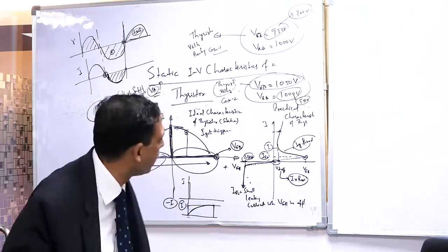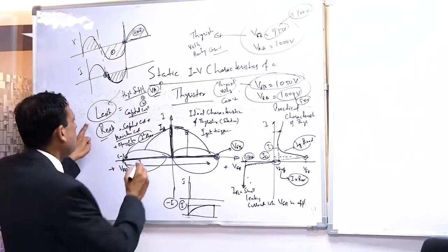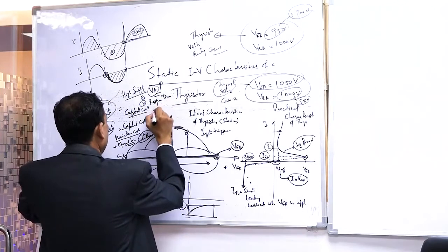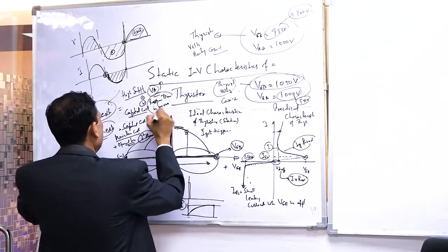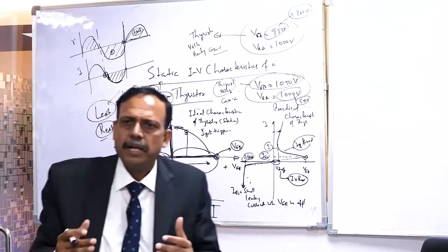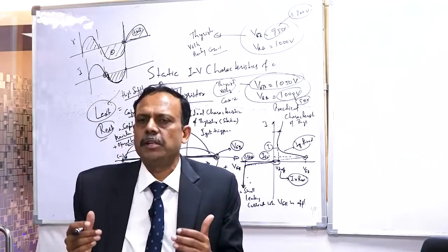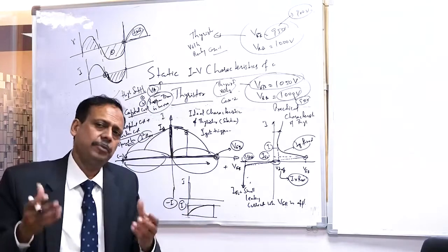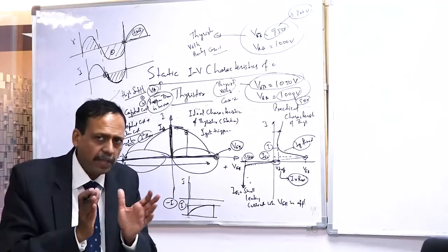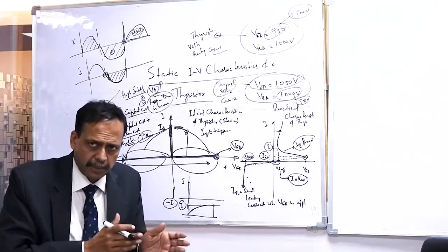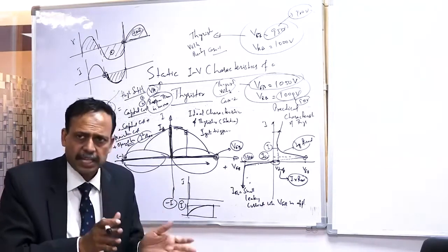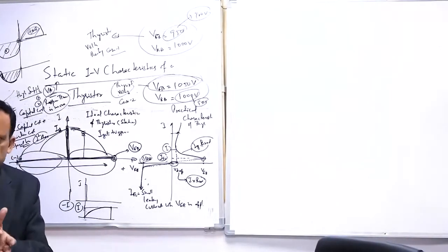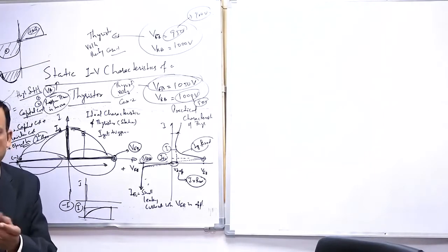Response time is poor when the inductance is used. Response time is more, which is not good. By using an inductor, we are slowing down the system. But yes, we can use a thyristor of smaller rating. So indirectly we are saving cost. So we have to make a trade-off between the cost of the thyristor vis-a-vis the cost of the external R and L and the operational cost linked with the external R and L.